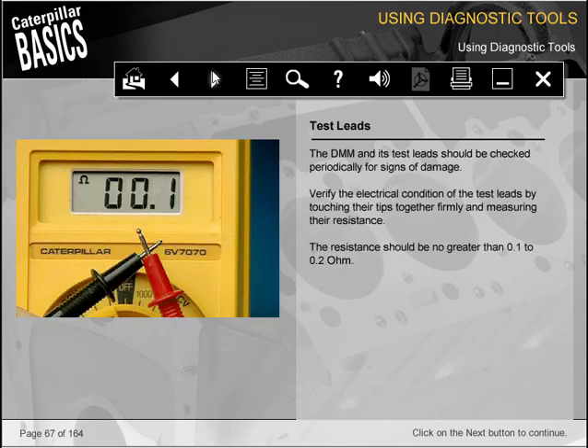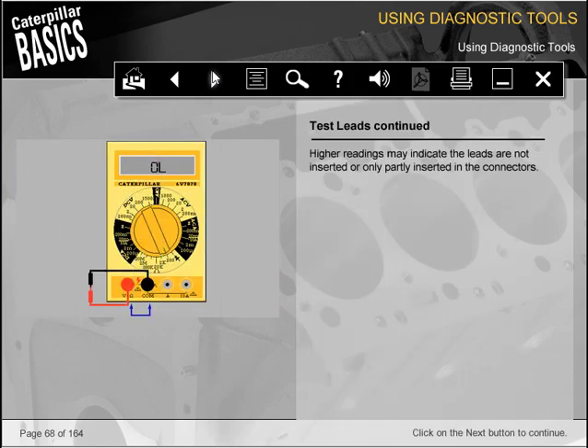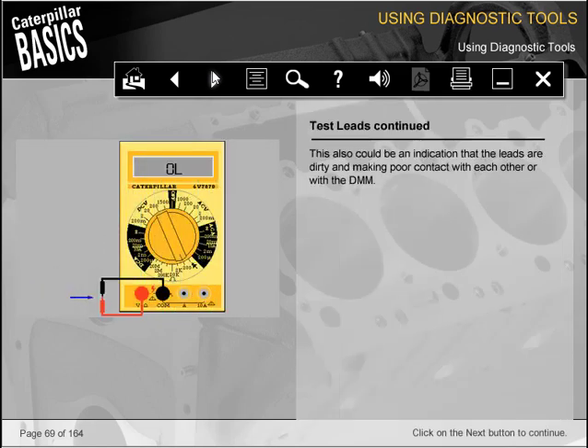The DMM and its test lead should be checked periodically for signs of damage. Verify the electrical condition of the test leads by touching their tips together firmly and measuring their resistance. The resistance should be no greater than 0.1 to 0.2 ohm. Higher readings may indicate the leads are not inserted or only partly inserted in the connectors. This also could be an indication that the leads are dirty and making poor contact with each other or with the DMM.